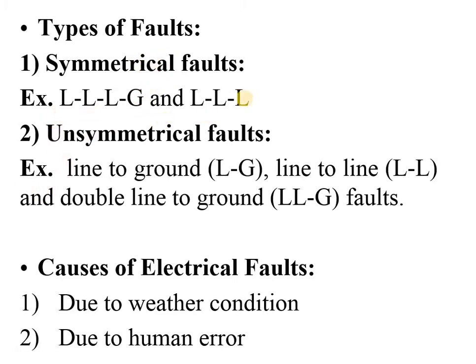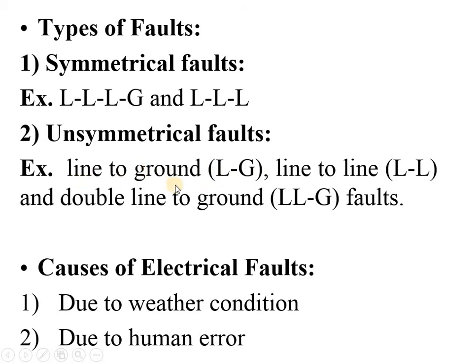Unsymmetrical faults include line-to-ground fault, line-to-line fault, and double line-to-ground fault. The majority of faults in the power system are unsymmetrical — about 85 to 90 percent. Among these, line-to-ground fault plays the most important role, accounting for about 80 to 85 percent of faults observed in the power system.